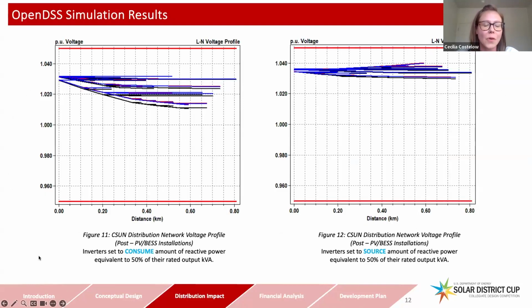Thanks. So if we wanted to change that system, we actually have some control over that by adjusting the reactive power output from the inverters that we use. So we use Chint power inverters for most of our installations. They're smart inverters that allow us to change the reactive power output. So if we set those inverters to consume a certain amount of reactive power, then we're able to bring the voltage profile of the system down. And conversely, if we want to increase the voltage profile of the system, we can set those inverters to source a certain amount of reactive power.